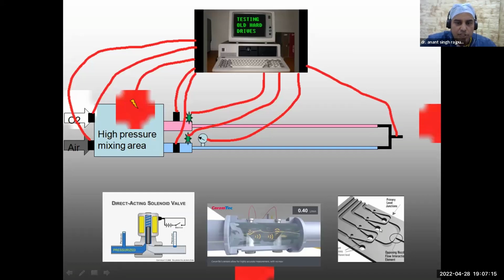There are various valves. This is a fluidic valve. This is a solenoid valve. So various types of valves are used to control the flow from high pressure. Generally for high pressure, we use fluidic valves, right? So fluidic valves are up there, which ultimately mix the gases in a certain area. From there, the oxygen sensor is there, which again feeds to this.